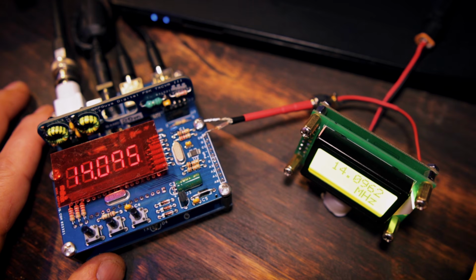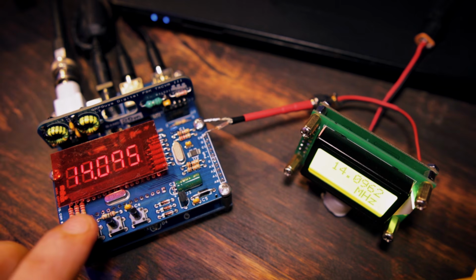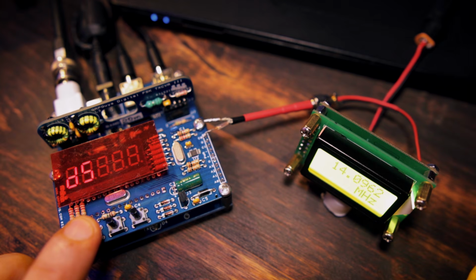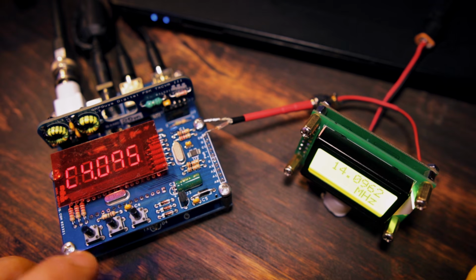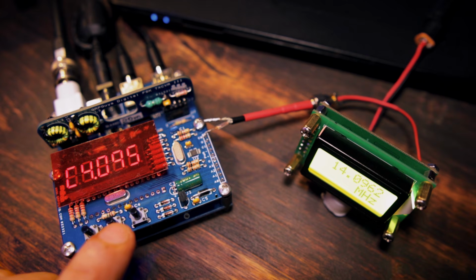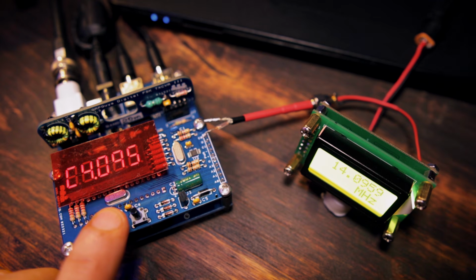It's 14.0962. It's supposed to be 960. So I'm going to hold this button for about 12 seconds and it will go into the calibration mode. If you hold it longer, for like 15 seconds, it will reset all the calibration adjustments that you've made in case you want to readjust everything. So right now I'm going to click this button and go low until my frequency counter will read 0960.